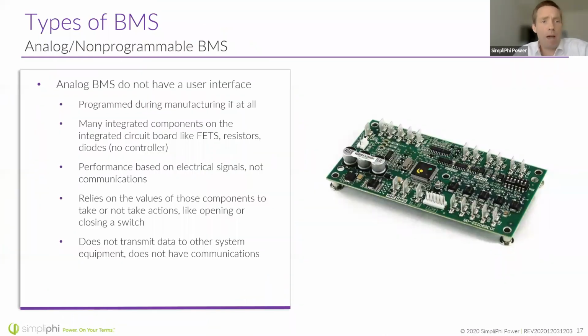The first type of battery management system is often referred to as analog, but it's really a non-programmable BMS. The big difference between the two is that one is programmable after it comes out of the factory, while analog units are programmed at the factory and you cannot adjust those settings.